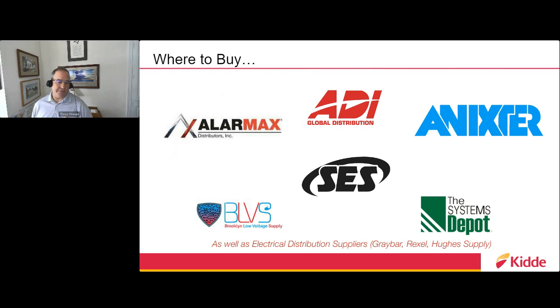The other option is that, depending on the jurisdiction, they may want a secondary path of communication, which could be cellular. You could also connect a Bosch dual path communicator to the onboard dialer and have that communication path go to an IP receiver and/or through cellular communication back into a central station. So there are a couple of different options there, and the answer to the question is yes.